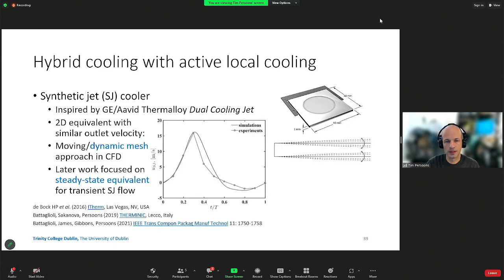The synthetic jet cooler that we decided to model was one developed by General Electric, or now taken over by Aavid Thermalloy, the so-called dual cooling jet. It's a synthetic jet which is basically two flexing membranes. You have two piezoelectric actuators oscillating these two membranes, and that will cause a synthetic jet to form at the outlet of this slot over here.